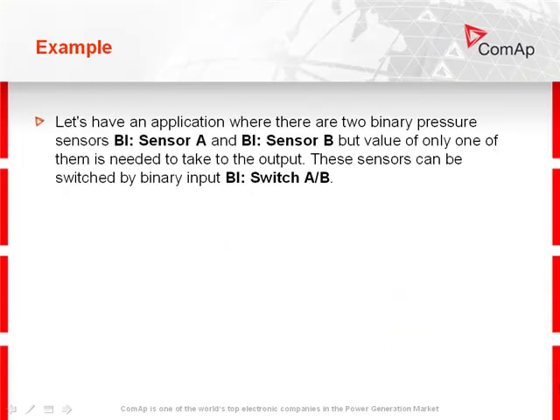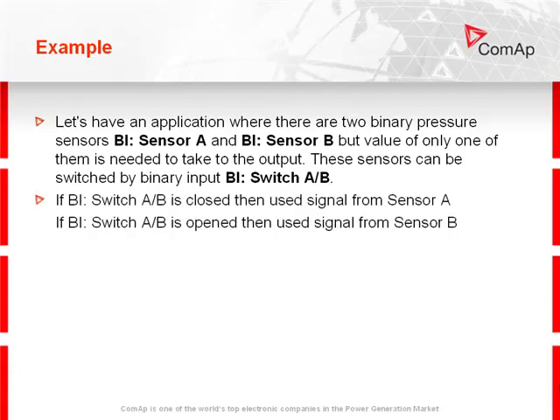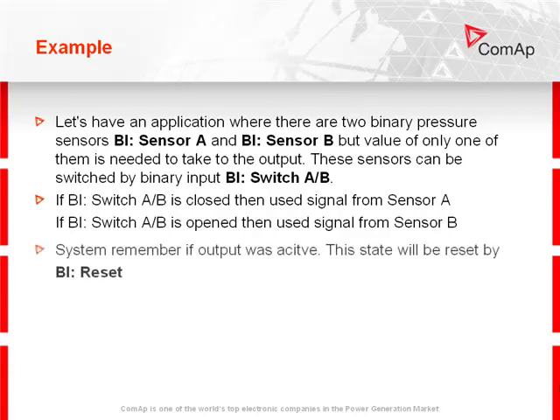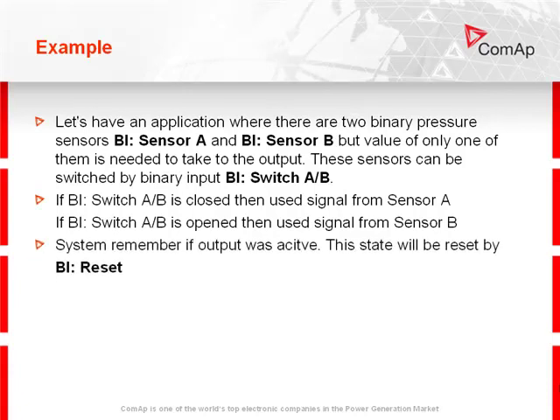Now we use these functions in an example. Let's have an application where there are 2 binary pressure sensors: binary input sensor A and sensor B. Only one of them is needed at the output at a time. These sensors can be switched by binary input switch AB. If switch AB is closed, the signal from sensor A is used. If switch AB is open, the signal from sensor B is used. The system remembers if the output was active, and this state will be reset by binary input reset.